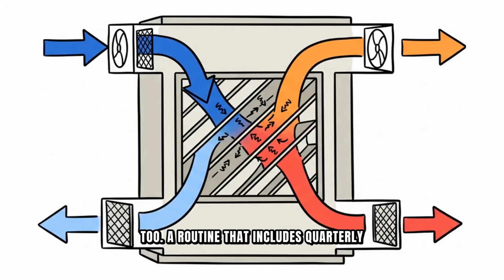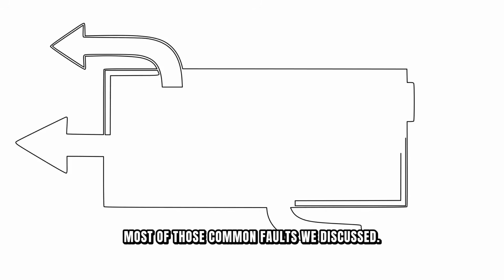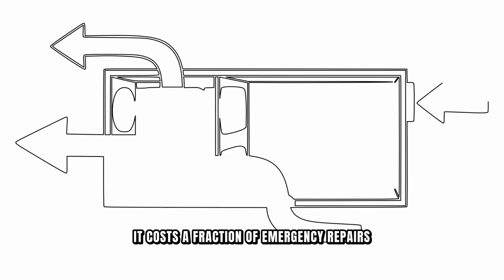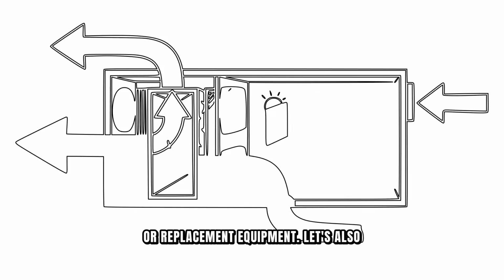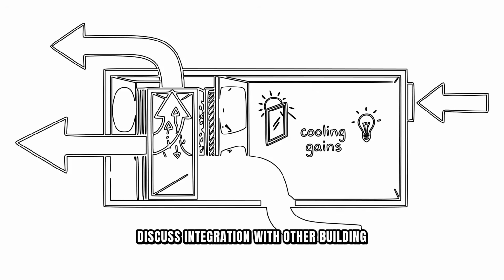Preventive maintenance makes an enormous difference too. A routine that includes quarterly filter changes, annual belt inspection, semi-annual coil cleaning, and regular sensor calibration prevents most of those common faults we discussed. It costs a fraction of emergency repairs or replacement equipment.